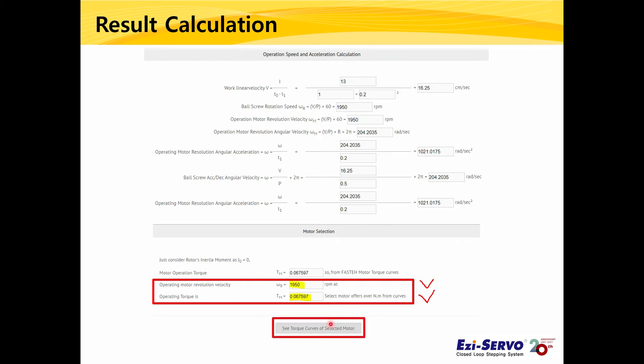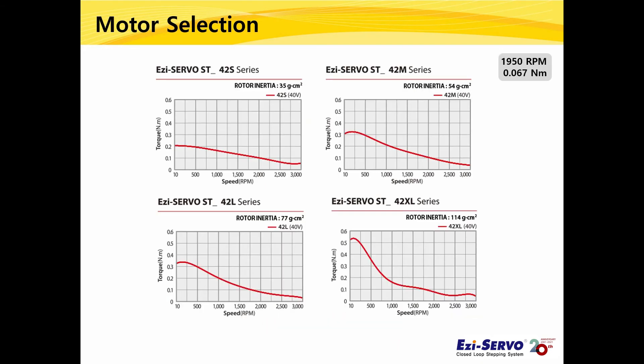Click the button here to see the torque graph of the motor. Torque graphs from 20 to 86 mm size motors will be shown. Since we decided to use a 42 mm motor, let's check the data for 42 mm motors. The required result was a motor with torque larger than 0.067 Nm at 1950 rpm. In the case of 42 mm motors, all motors meet this condition at about 2000 rpm.